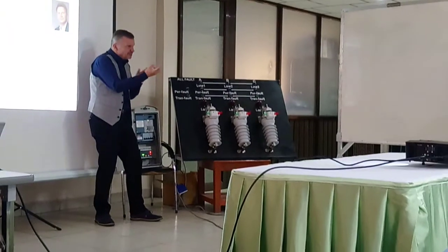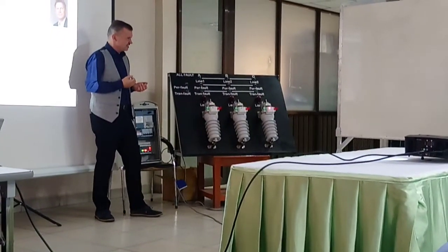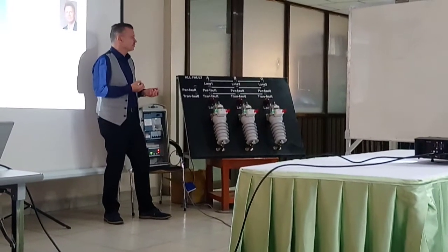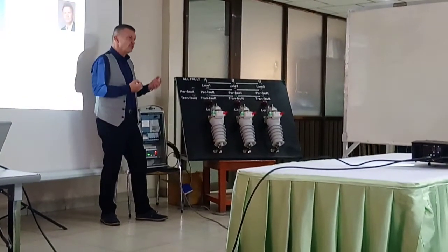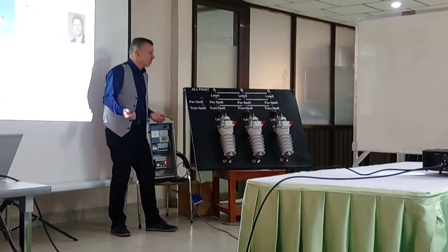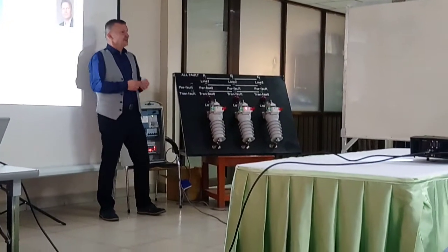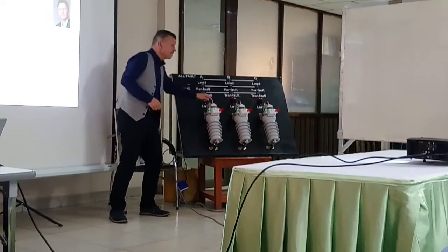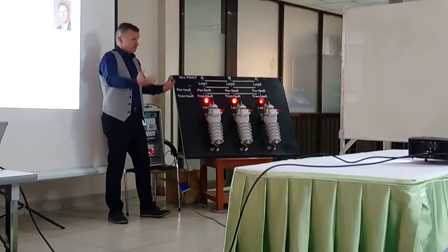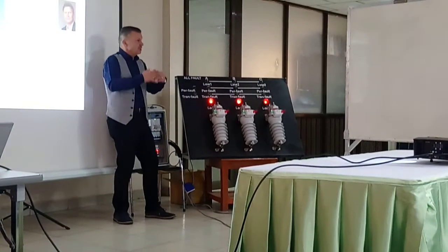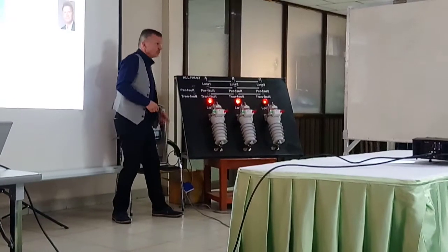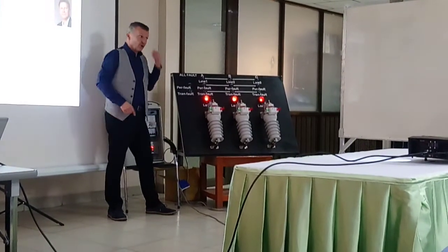I hear a little bit of concern about the 60 seconds, and I would like to understand where this concern comes from. Maybe I'm wrong, but usually that's outage time. The outage time takes maybe 1-2 hours. So the line crew goes on site, repairs the line because of the permanent fault. In other cases, you don't need to operate it manually. So the line crew has repaired the fault, put everything together, and then you have to press that red button, or that one, or use the software, or call the SCADA.